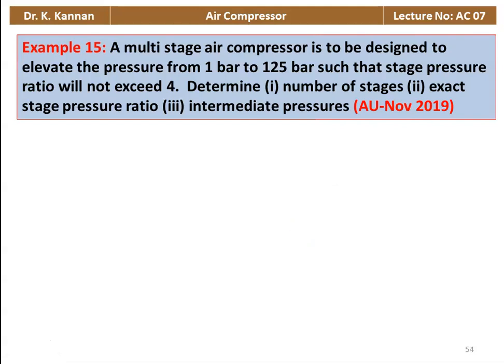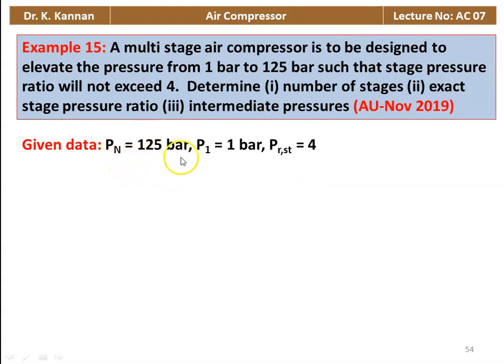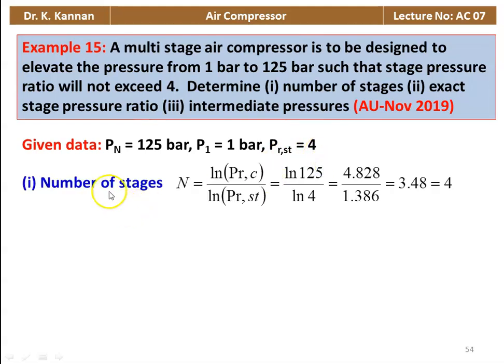Example number 15 from November 2019. A multi-stage air compressor is designed to elevate pressure from 1 bar to 125 bar such that the stage pressure ratio does not exceed 4. Determine the number of stages, exact stage pressure ratio, and intermediate pressures. Given: Pn = 125 bar, P1 = 1 bar, max pressure ratio per stage = 4. Number of stages = log(125) / log(4) = 4.828 / 1.386 = 3.48, rounded up to 4 stages.